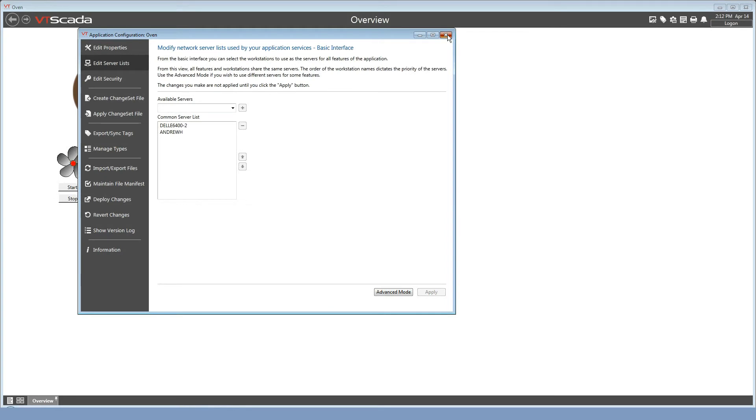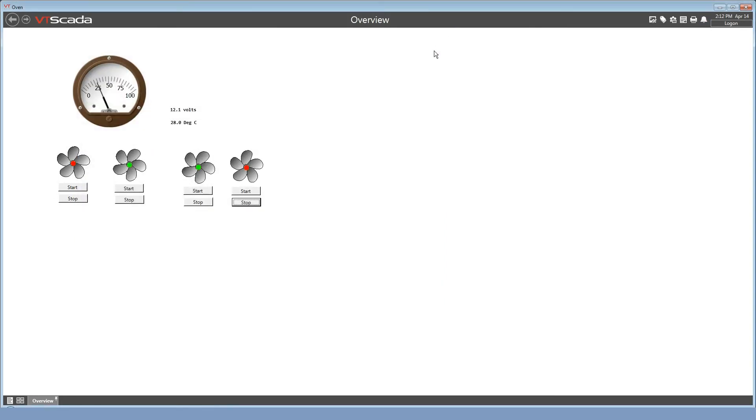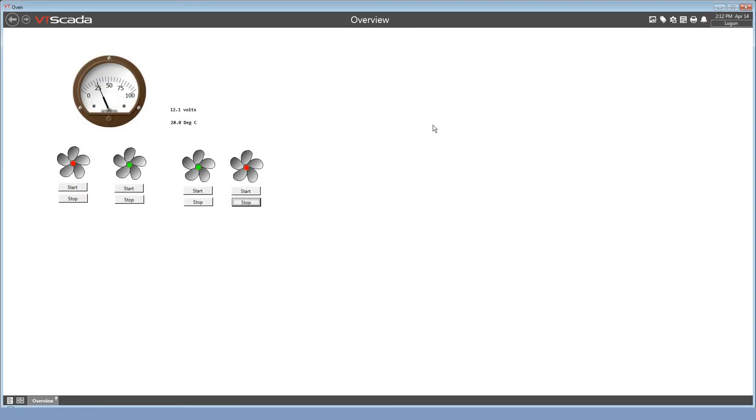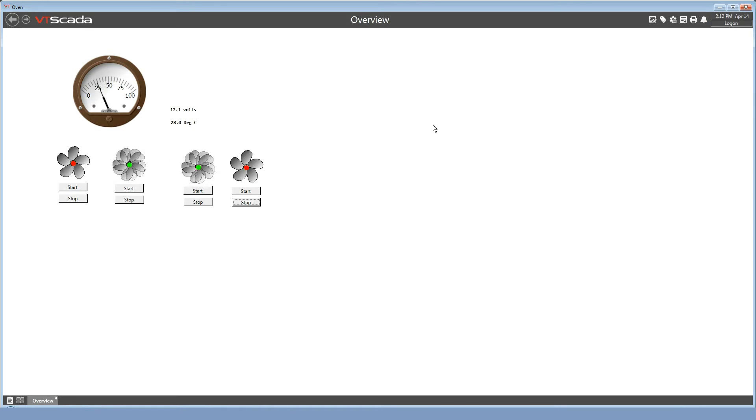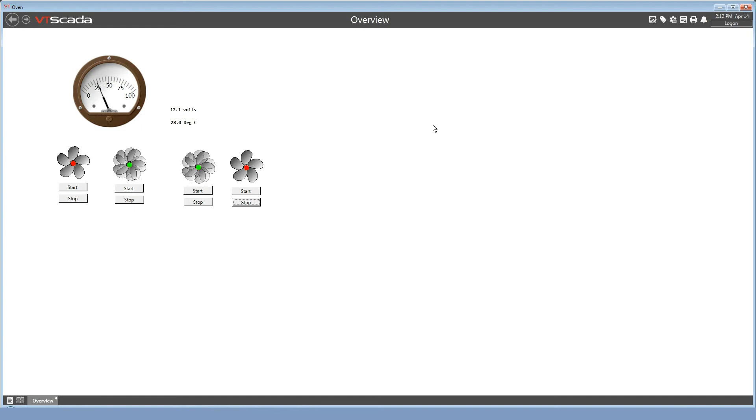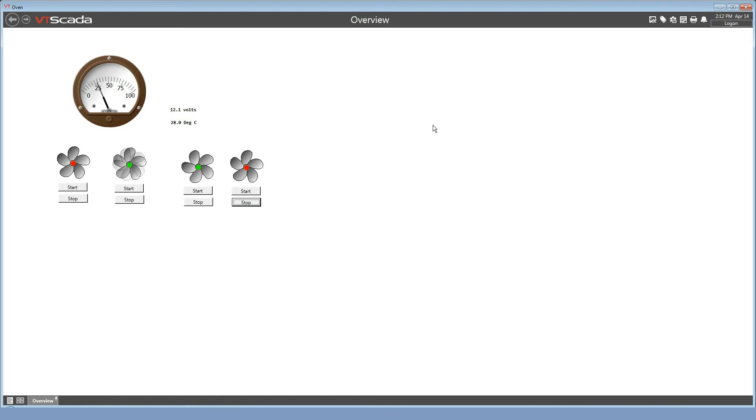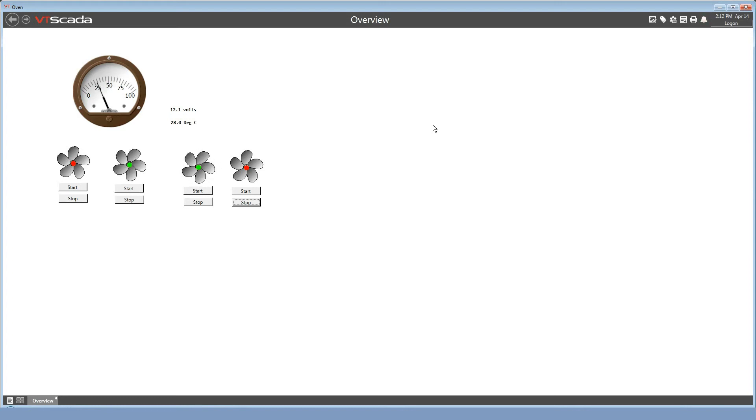I can now close my application configuration, and in the background, VTScada is in the process of copying all of the log files from the primary to the backup. Now up until now, only the servers keep log files and any other recorded information. So even though this computer was running the application, it was not storing any of the log files. Now that it's a backup server, it will have a complete copy.